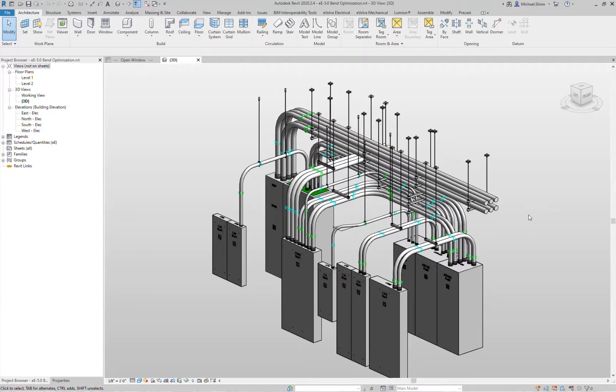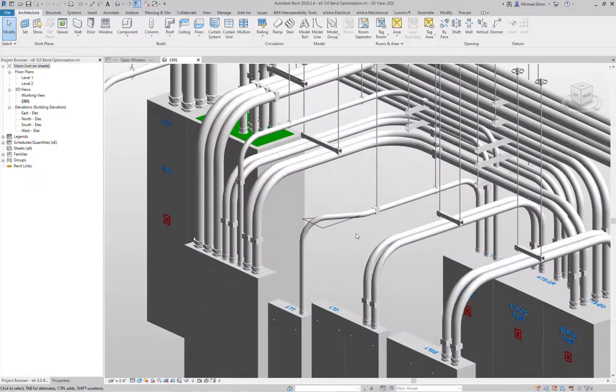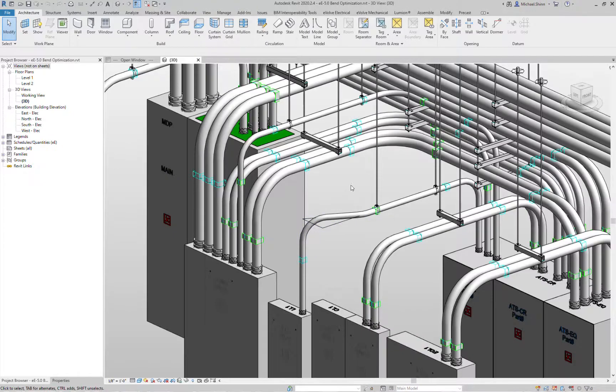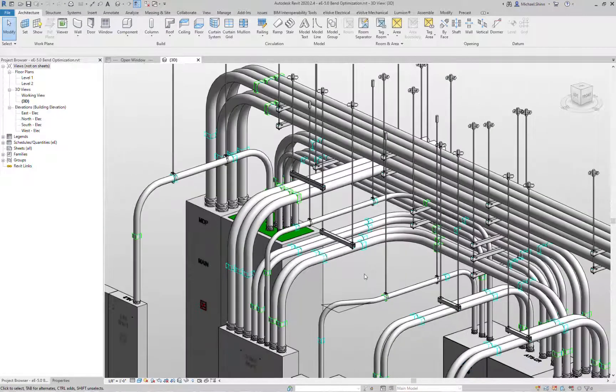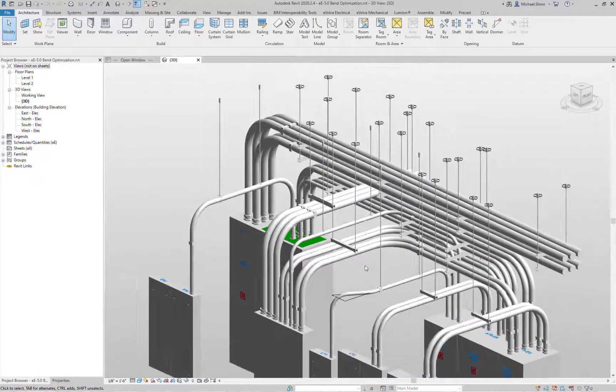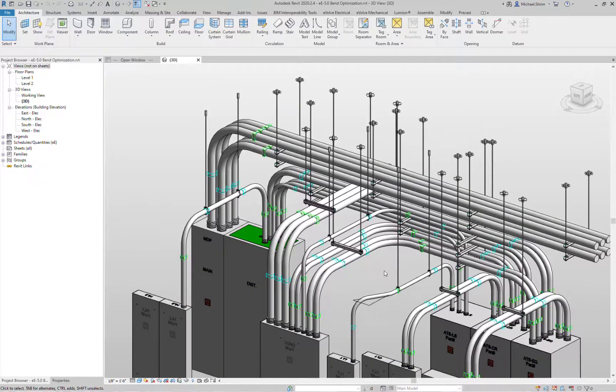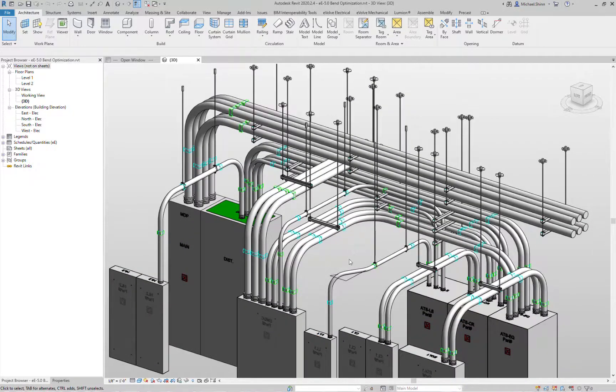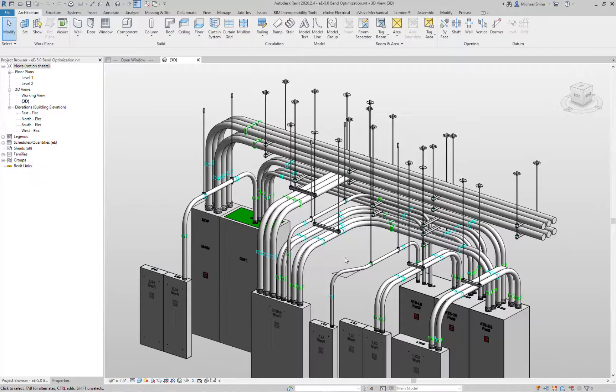At this phase of the project, our recommended workflow is: don't worry about optimizing and placement of couplings during the drawing phase. Draw in all your conduits, get them all in as fast as you can — faster than the pipe and duct guys — and then once that area or portion of the model has been signed off, go back and optimize your runs. At this point, the floor and switchgear room have been signed off, so we're now ready to optimize our runs and get these ready for spool drawings and out to the prefab shop.